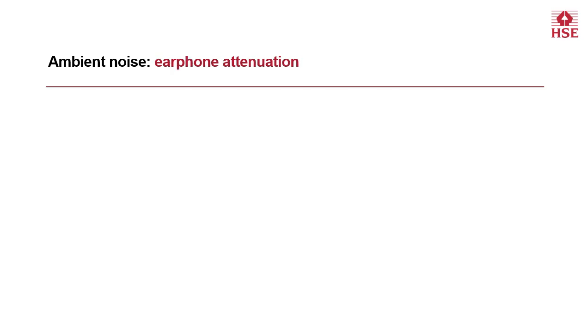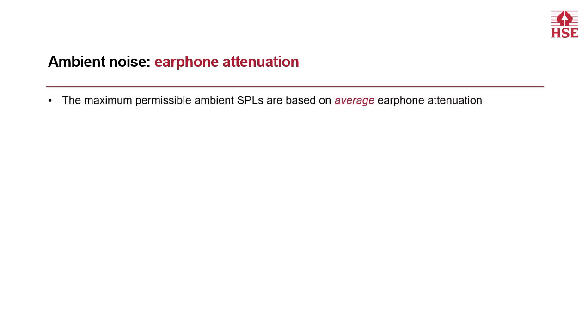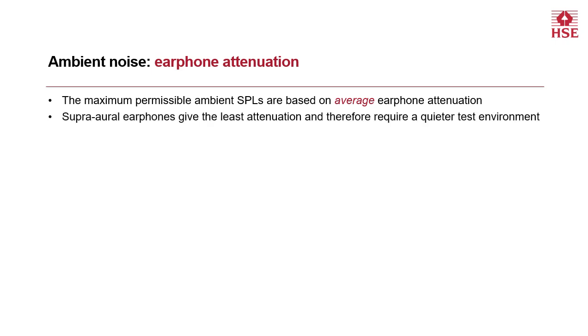Now let's consider how earphone attenuation affects this picture. The maximum permissible sound pressure levels are based on the average earphone attenuation. Supra-aural earphones give the least attenuation and therefore require a quieter test environment. But some listeners will receive less than the average attenuation, so you need to bear this in mind and reduce the ambient noise to as low as practicable.